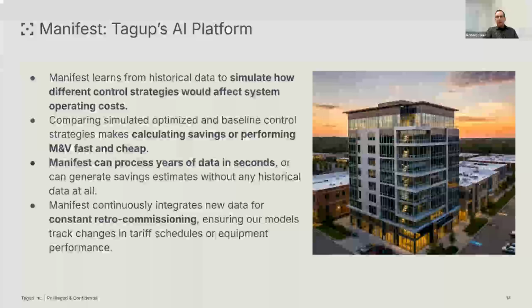Over time, the equipment changes and how it reacts changes too. It's also important to see how changing load patterns affect this, if a building starts to have different usage, for example at universities, which can be an important consideration in summer versus winter. None of these things are hard-coded anywhere or set via manual setting. We measure load implicitly, so any changes will directly be translated into how the system decides what to optimize.